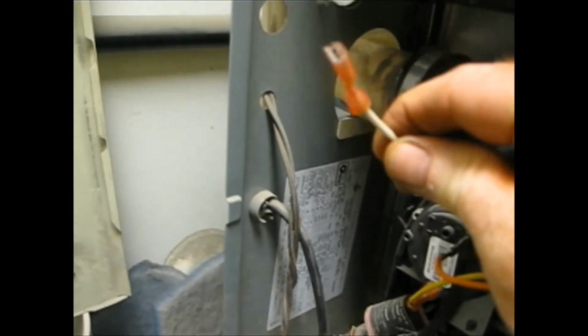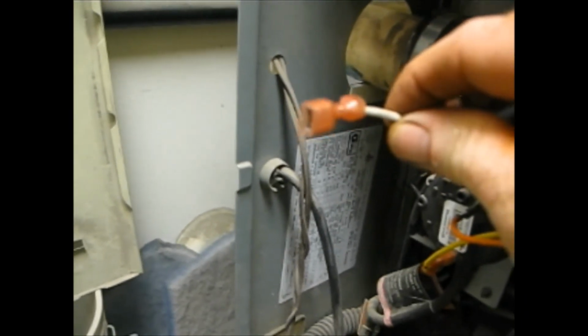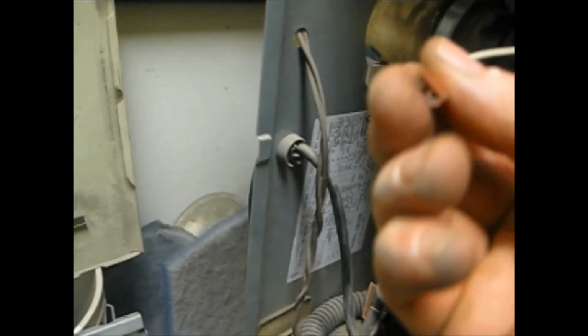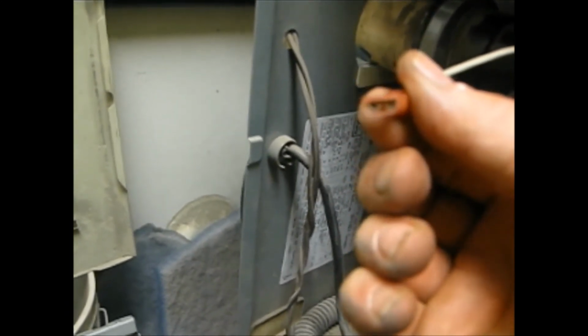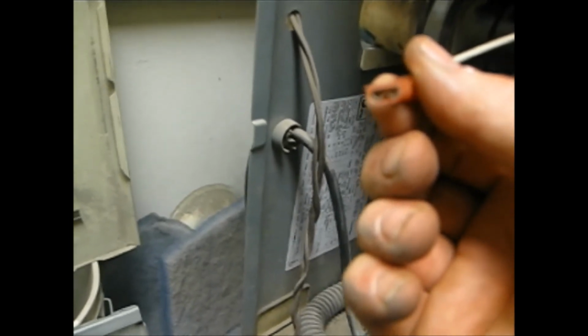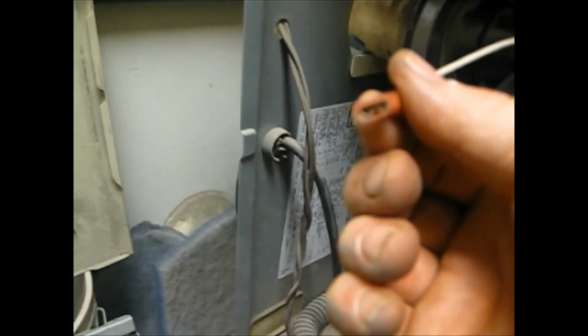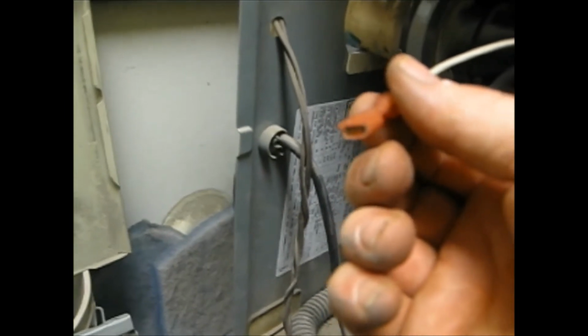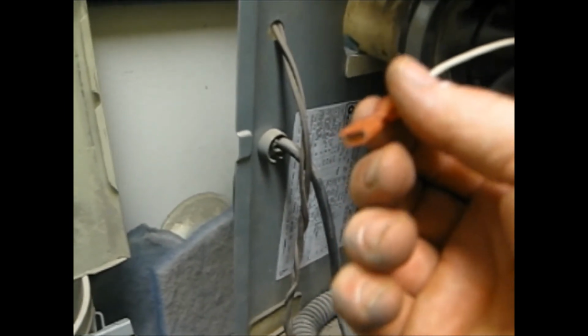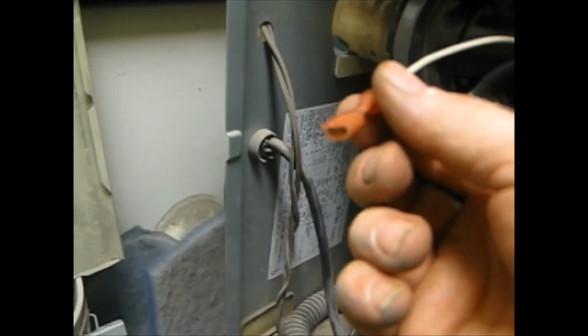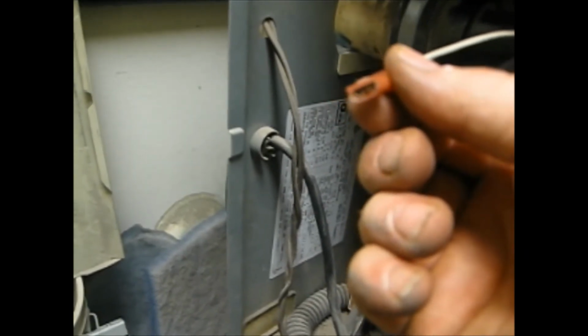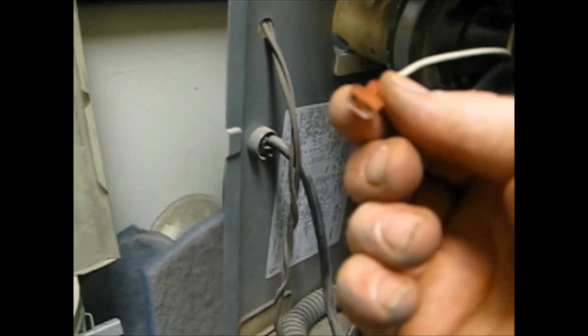Now, the flame rod doesn't accept power, it generates power, so there's no reason for us to try to probe for any power at this connection. It doesn't exist. The flame rod, by its nature, sends a certain amount of current back to the circuit board, so there's nothing here to test. In this case, we're going to go off the trouble codes.